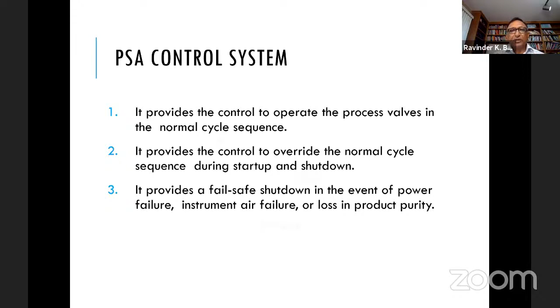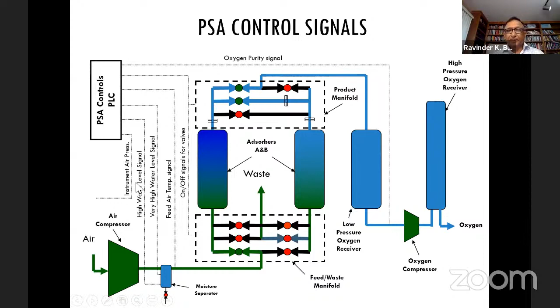I'll tell you how we do it. We take signals from all the valves, and signals from all the sensors we put in the plant. These depend on the application and what the user wants. We bring all these signals to a PLC controller, and then we can program it any way the user would want it to be, depending on what he thinks is important. That's how the PSA plant is controlled.